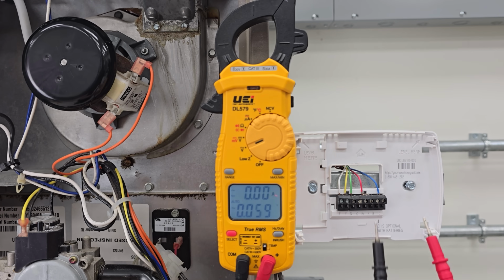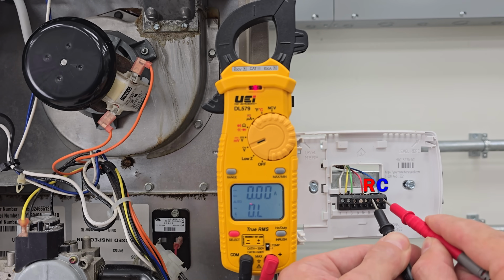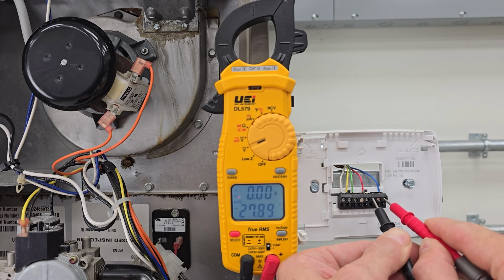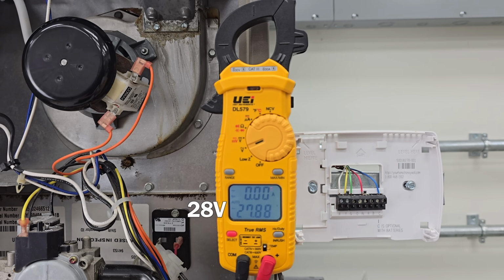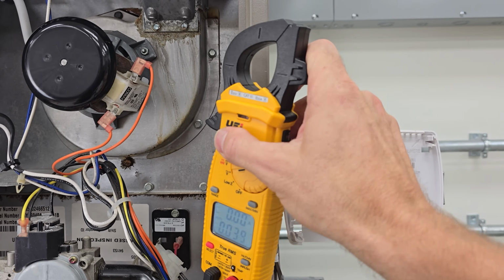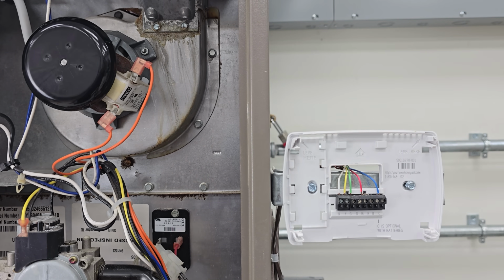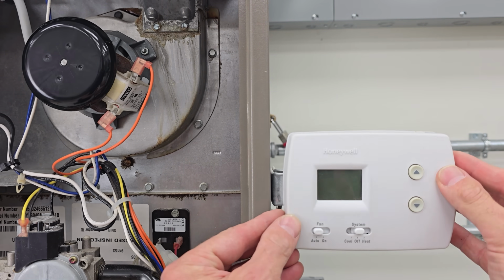Now we're going to check for 24-volt power between the R and the C terminal. And you see we're measuring just under 28 volts. So we can remove our multimeter and put our thermostat on, and it should now light up.